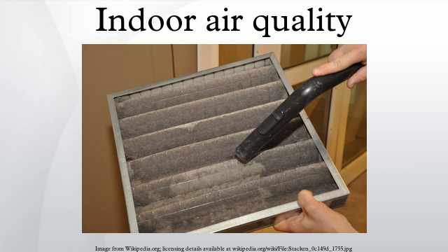Exhaust gas leakages can occur from furnace metal exhaust pipes that lead to the chimney when there are leaks in the pipe and the pipe gas flow area diameter has been reduced. The use of air filters can trap some of the air pollutants. The Department of Energy's Energy Efficiency and Renewable Energy section wrote, "Air filtration should have a minimum efficiency reporting value of 13 as determined by ASHRAE 52.2-1999." Air filters are used to reduce the amount of dust that reaches the wet coils. Dust can serve as food to grow molds on the wet coils and ducts and can reduce the efficiency of the coils.